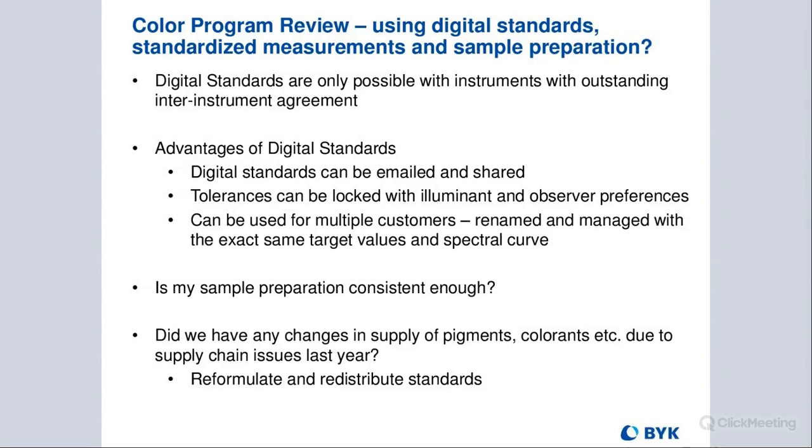So consistency and sample preparation for our standards is very, very important. And if we have reformulations due to supply chain issues, really at that point you should reissue your digital standard because your formulation has changed. The other thing that's important, and you can't do this without it, is your inter-instrument agreement has to be very good in order to do digital standards.